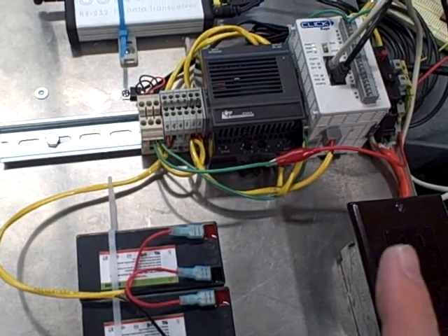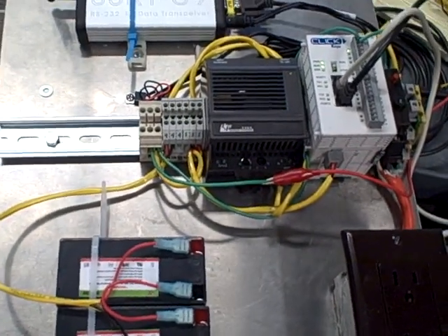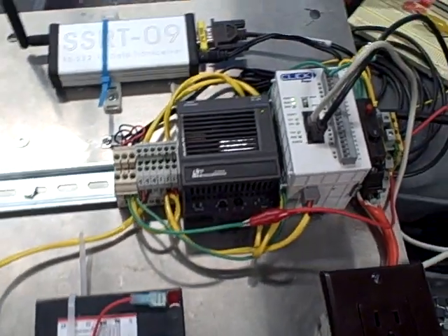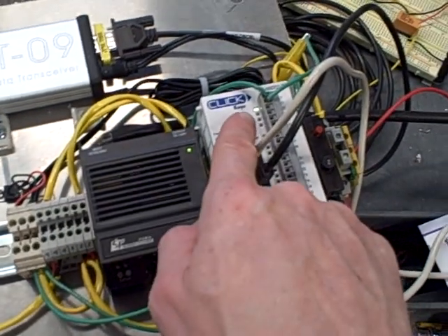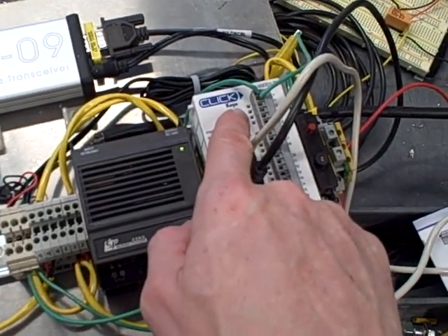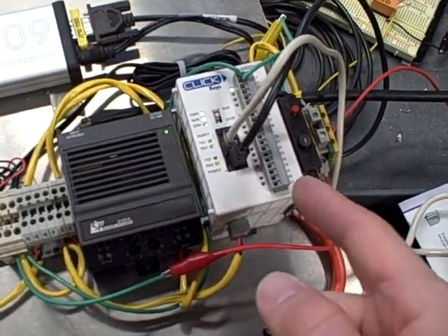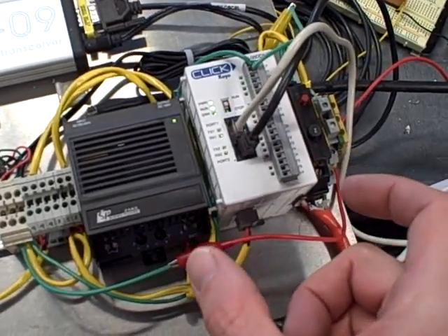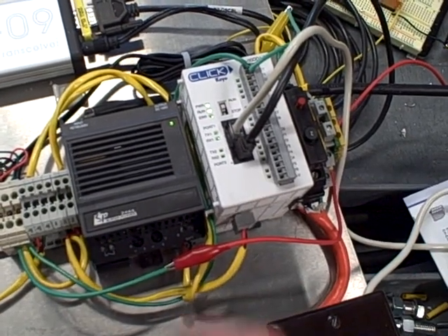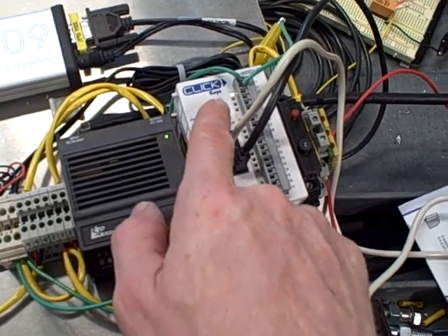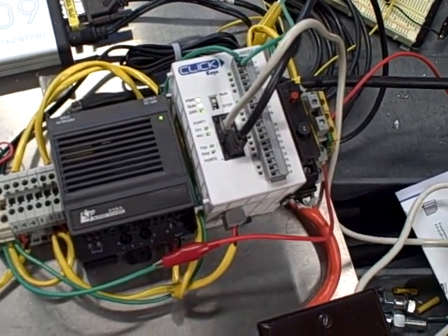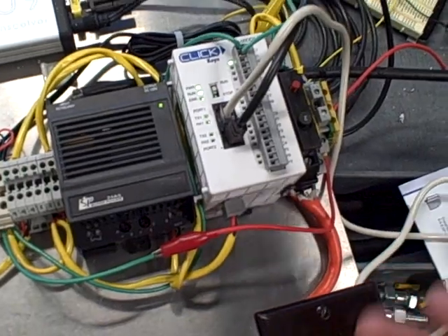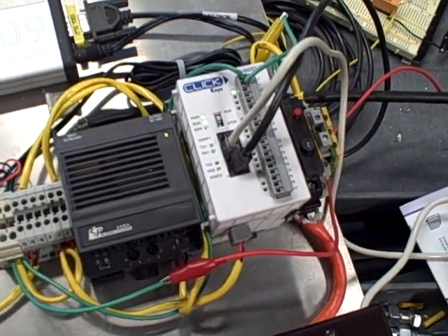We're doing burn-in testing, making sure all the components are working the way they should, as designed. So the PLC receives the pulse input from the flow meter, does some calculations over time over set intervals to calculate gallons per minute. Each pulse of the flow meter represents one gallon. So 30 pulses in a minute would be 30 gallons per minute.